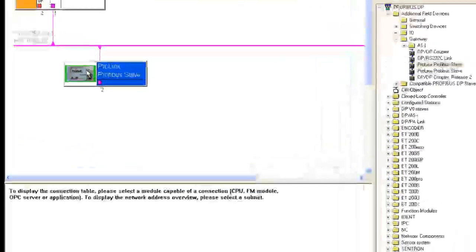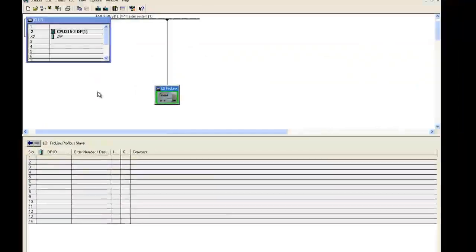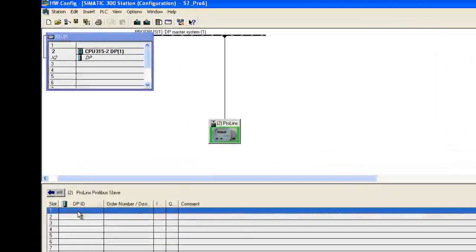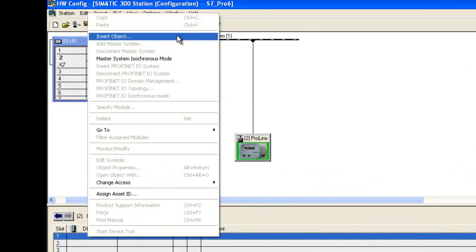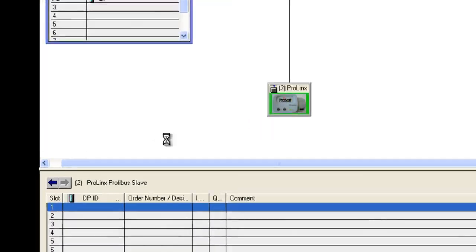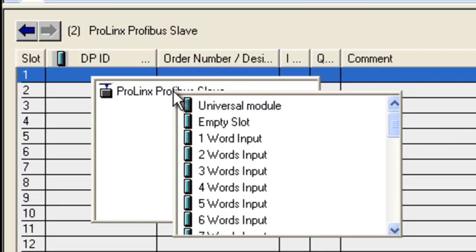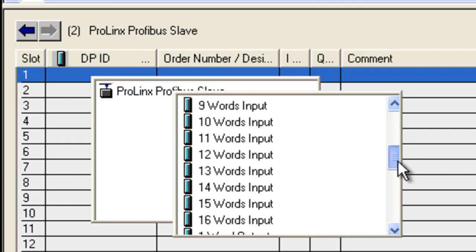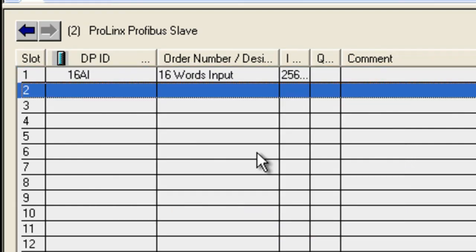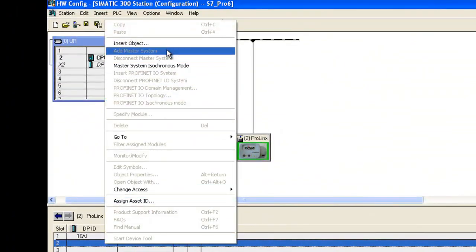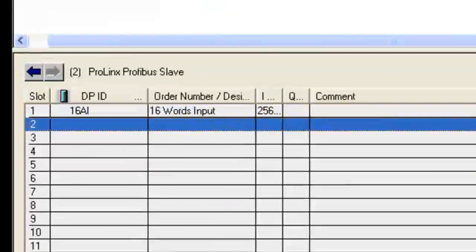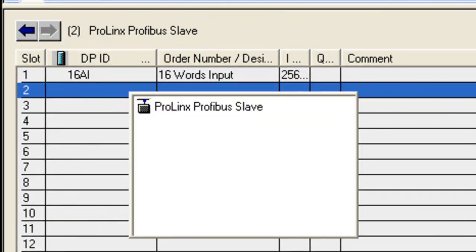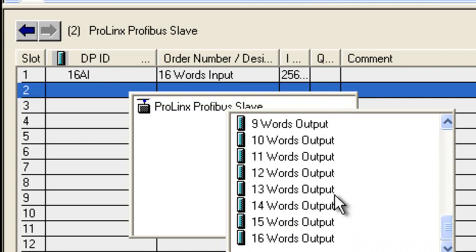Now we're going to edit our ProLinx. This is where we're going to be adding the modules for that ProLinx. So we'll right click on the first available slot, Insert Object. And that will open up a dialog box. We'll select ProLinx Profibus Slave and we're going to go ahead and grab 16 words of input. And we're also going to do the same for slot 2. We're going to go ahead and insert an object, but this one's going to be 16 words of output data. So it'll bring up that same dialog box and we'll just drill all the way down to 16 words of output data.